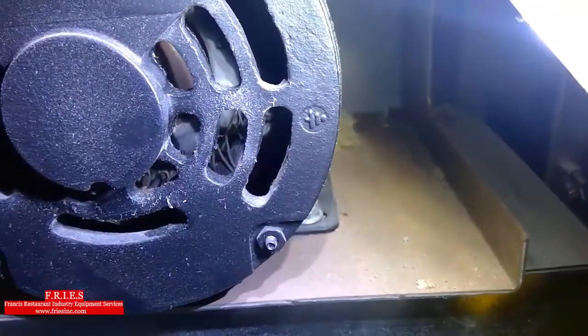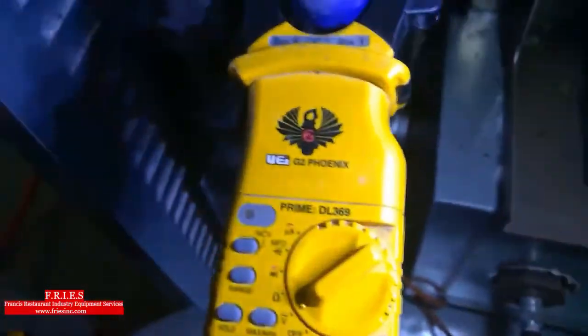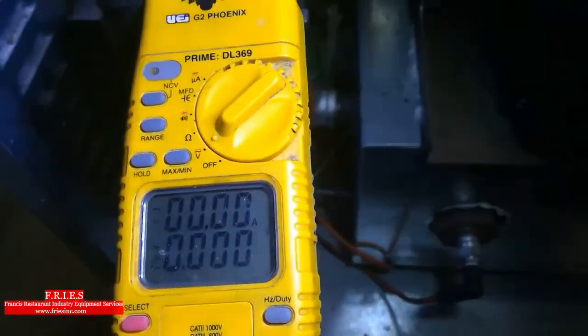Alright, so I'm testing power into my module. I have 21 volts. The burner is running. My blower is running. So I just need to be patient here, wait for the intermittent problem. Alright, my blower just changed directions. My burner did not fire up. I have 0 volts at the module.